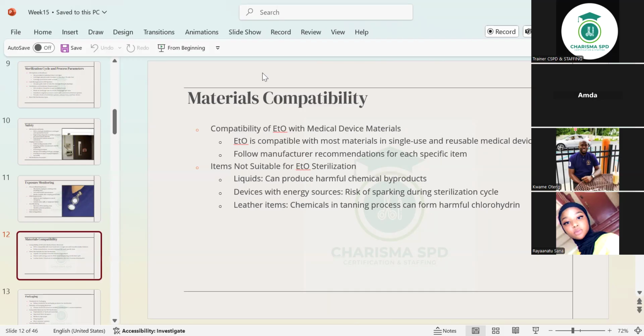Items not suitable for ETO sterilization include liquids, which can produce harmful chemical byproducts, and devices with energy sources, like batteries, because of the risk of sparking during a sterilization cycle. Leather items too: the chemicals in the tanning process can form harmful byproducts that will come out of it and be very toxic. So the three things that cannot go in ETO sterilization are liquids, devices with energy sources, and leather items.